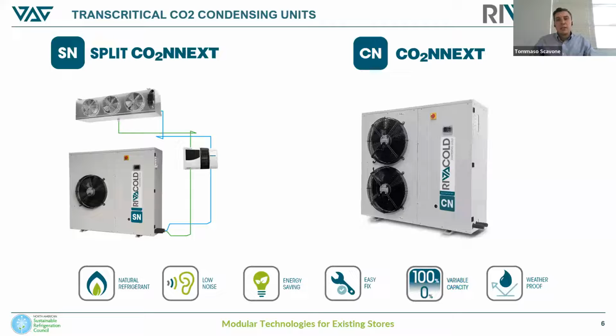as a single condensing unit can be connected up to 5 different applications, such as a lineup of wall display cabinets, islands, regions, or any other merchandiser. It's completely weatherproof, so it can be installed outdoors on the roof or also on the side of the building, but also extremely silent, so allowing indoor installations if required, thanks to the reduced noise levels.